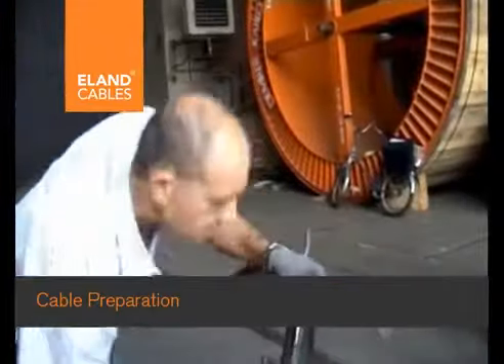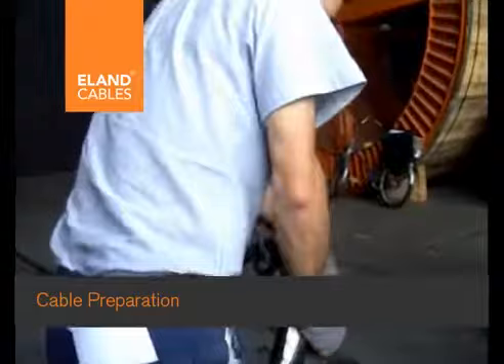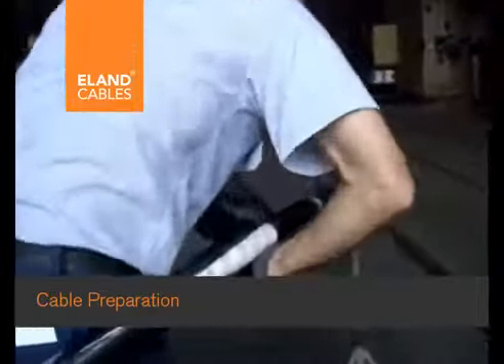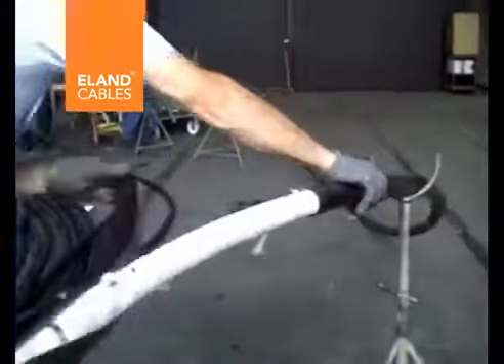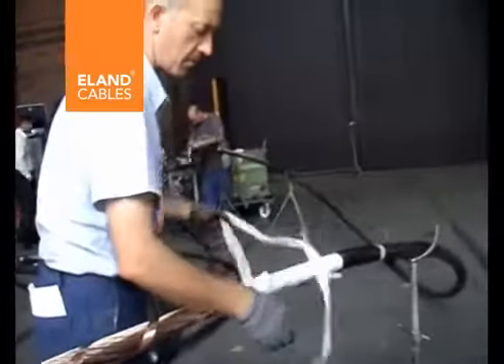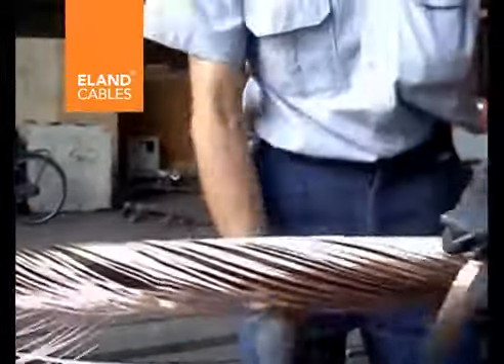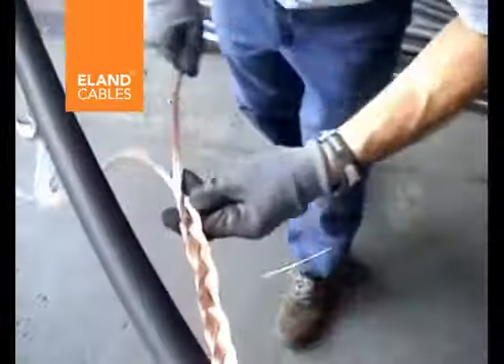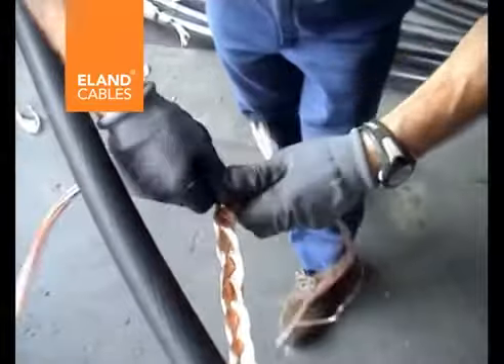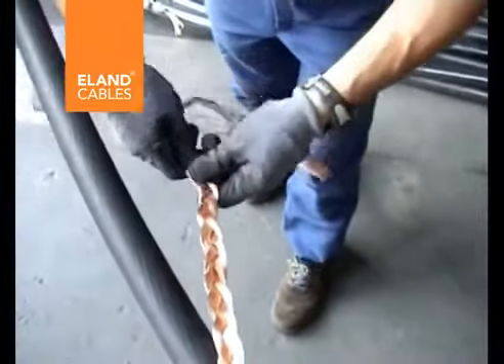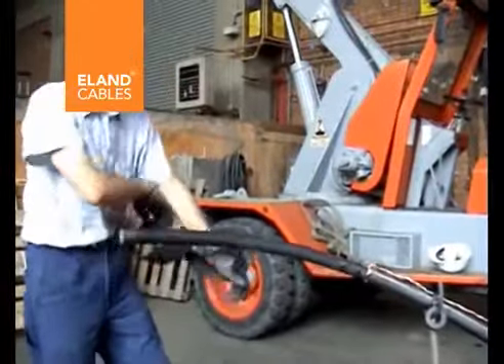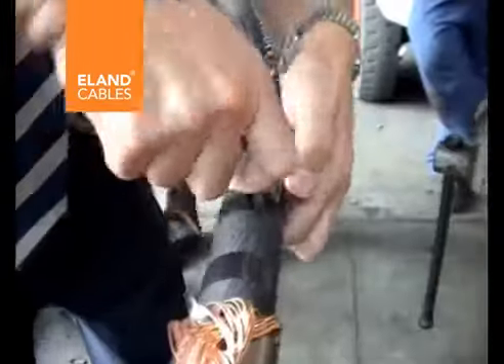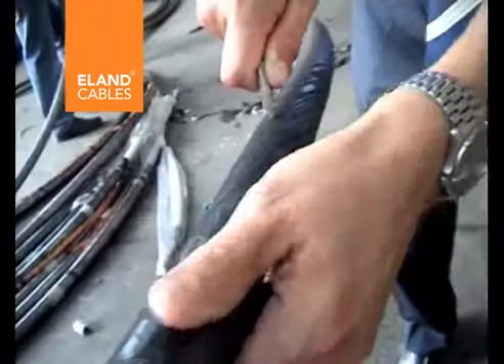What does this mean in practice? To begin with, the heavily graphited MDPE sheath was stripped back 600 mm to reveal the water-blocking tape. The equalizing tape was removed, before which the copper screen was formed into a pigtail to ensure optimum connectivity during the test. The bedding tape was unwound, uncovering the insulation screen, or semiconducting layer.